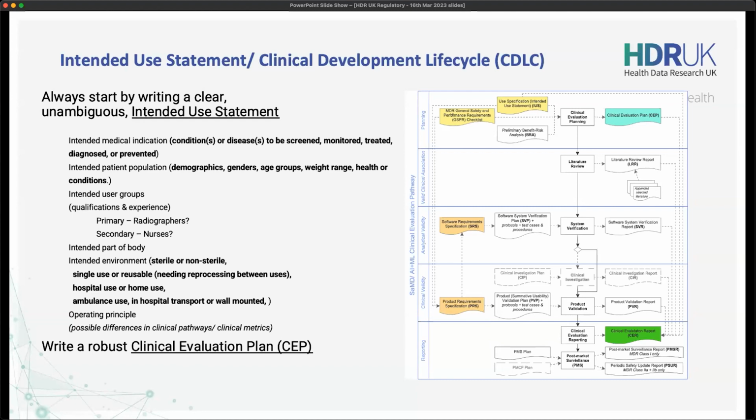So we talk about SAMD, so we often talk about AI or other techniques. Number one, how far are you stretching the term AI? Are you using decision trees, directed acyclic graphs, to traverse a set of inputs that deterministically get a set of outputs? Are you using deep convolutional neural networks? Are you doing some stochastic thing with statistics of a population to predict something for a patient? What are you doing? We like to know all of this, because then it leads into the clinical evaluation pathway.